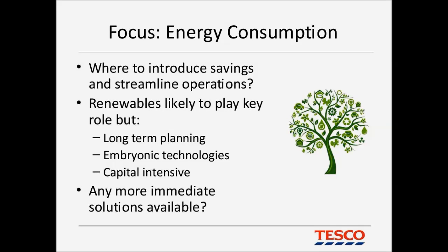We are currently this year planning major expenditure on energy-led initiatives that are forecast to provide us with a 110 gigawatt-hour part-year saving effect. That's a huge saving, most of which is related to conversion from T5 lighting to LED. LED has come on a lot in the last few years, and the improvement in technology has led us to a point where we are doing a lot of conversion work. Also, CO2 natural refrigerants. This is now a standard for all our new stores and is a big part of the plan to reduce carbon consumption due to its GWP index of 1 when compared to 3,300 for R404A, which is the most commonly used refrigerant in our stores.